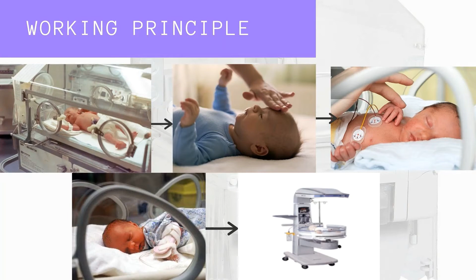Next is preparation of an infant incubator. Before we can use an infant incubator, a preparation is needed. Pre-warm to the desired temperature based on the infant's age, size and condition. Use air mode and calibrate the motor once if it is in use for a baby. Check and record the temperature, humidity and oxygen levels. Ensure that the alarms are working automatically. No equipment is placed on top of the canopy. These are the basic preparations needed before we use an infant incubator.